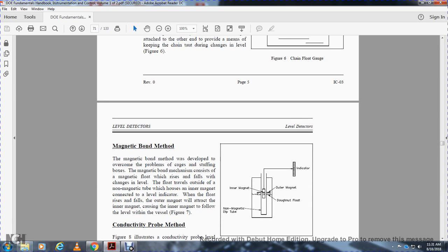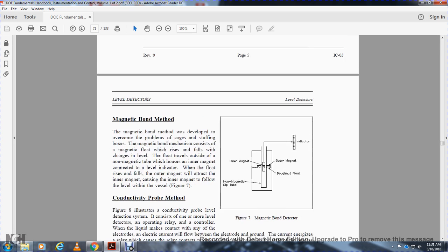The magnetic bond method was developed to overcome the problems of the stuffing box. Consider the magnetic float: as the float rises and falls with the level, it travels on the outside of the non-magnetic tube, which houses the inner magnet of the level indicator. The rise and fall of the outer magnet attracts the inner magnet, causing the inner magnet to follow the level of the vessel. Figure 7 shows the magnetic bond detector, with the indicator, the outer magnet, the donut float, the inner magnet, and the non-magnetic dip tube.